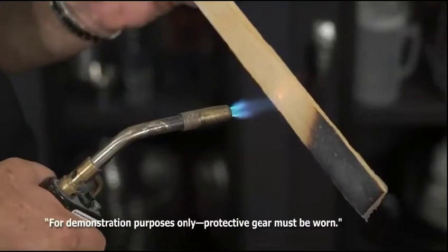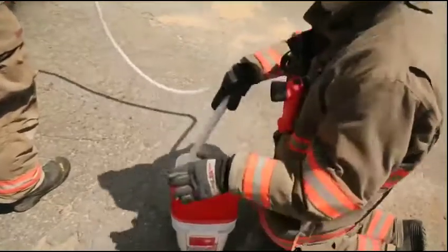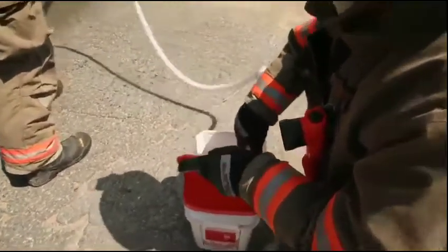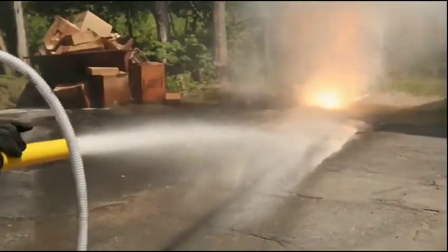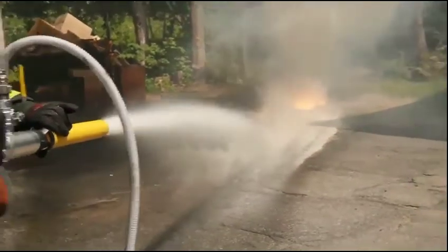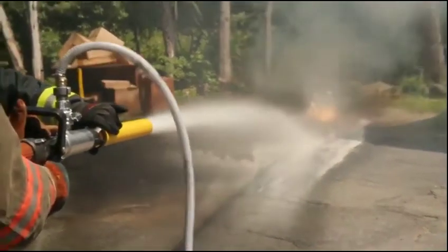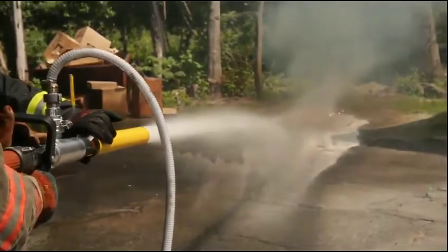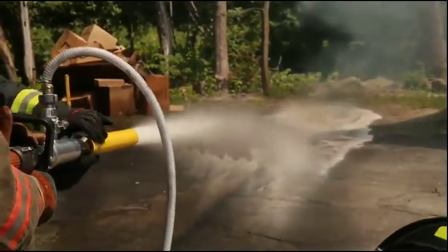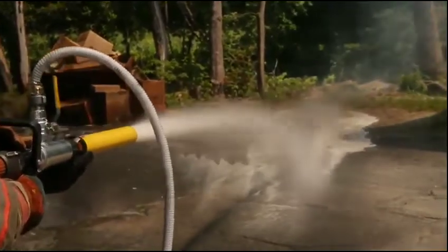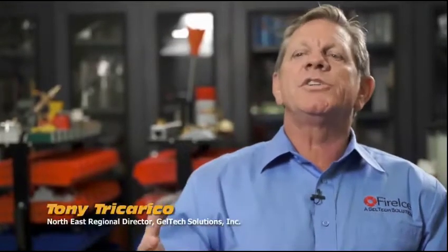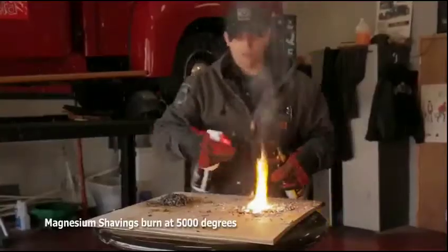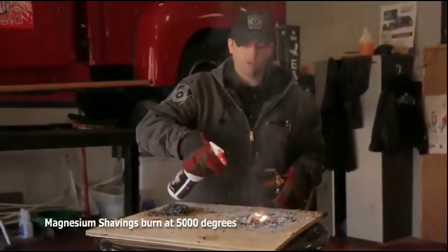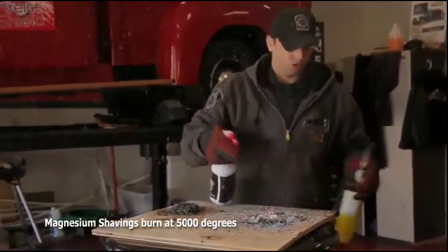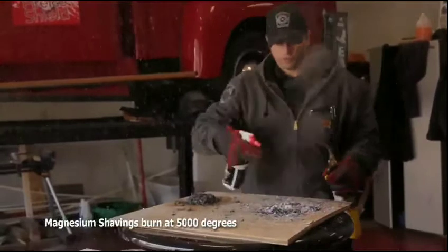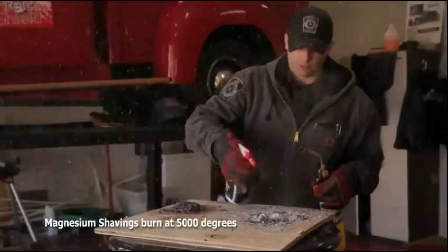FireIce can be used in extremely high temperature situations. It is highly versatile and is the only water-based product that can efficiently put out lithium battery fires, magnesium fires, electrical power substation fires, and other exceedingly high temperature situations for which water and/or foam are not durable enough. So let's take magnesium, for instance. Magnesium burns at over 5,000 degrees. FireIce is able to penetrate that heat to reach the fuel. By reaching the fuel and reducing it below its ignition temperature, it will stop the fire.